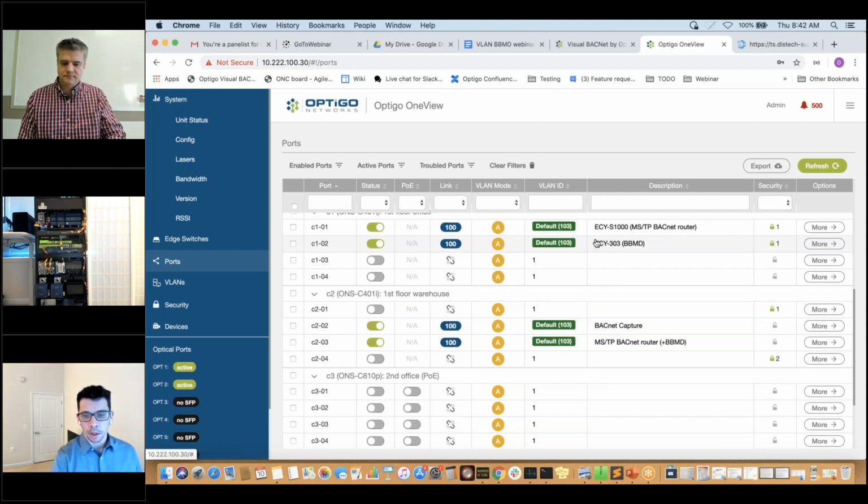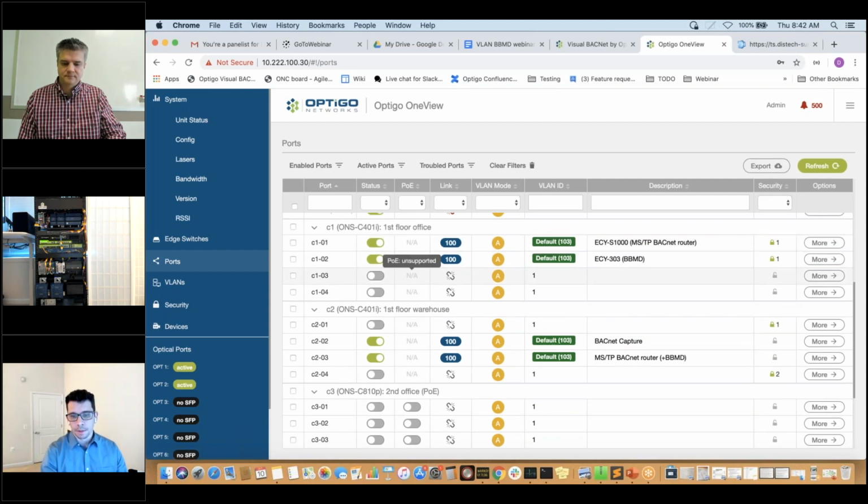And we want to stress really quickly that it's very common to look at VLANs and say, I have a Class C network, so 254 devices, and I'm just going to call that one VLAN. Or I have one floor, and I'm going to call that one VLAN. And that's not a great way from a design standpoint to look at the system. If you have tenants, sure, that might be what you have to do, but generally speaking, VLANs, we want to use those to segregate mechanical equipment or equipment that needs to talk directly to each other.